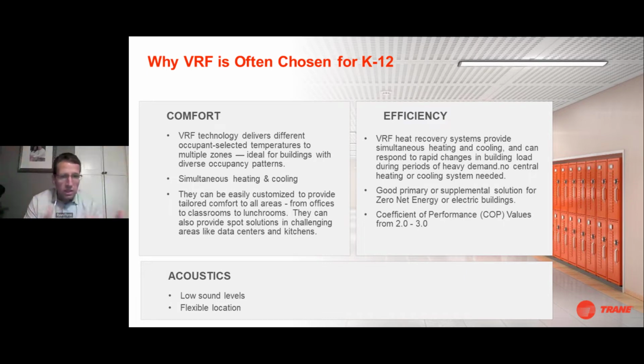Also delivers simultaneous heating and cooling. Can be easily customized and tailored to comfort all areas, from offices to classrooms to lunchrooms. It can even provide spot solutions for challenging areas like data centers and kitchens. Probably the number one reason: efficiency. VRF heat recovery systems provide simultaneous heating and cooling, and it can respond to rapid changes in building load during periods of heavy demand. And also, no central heating or cooling systems are needed. It's a good primary or supplemental solution for zero net energy buildings or electric buildings.